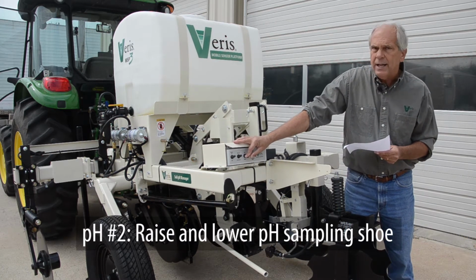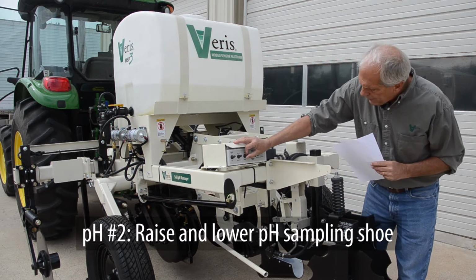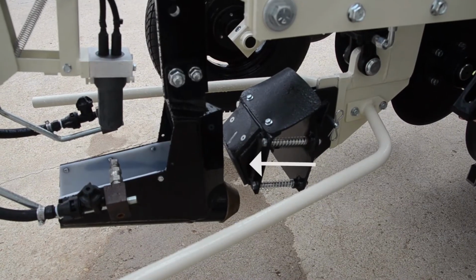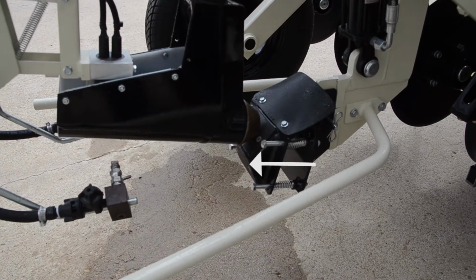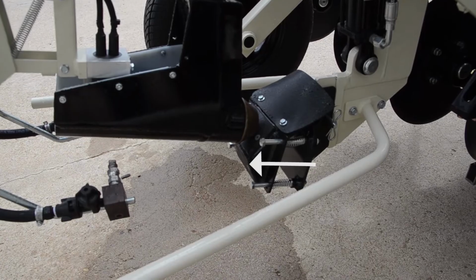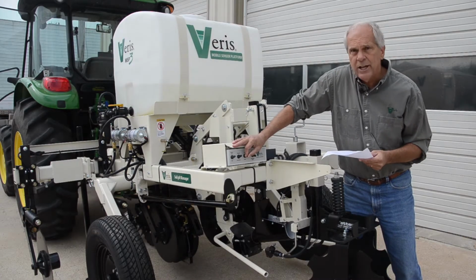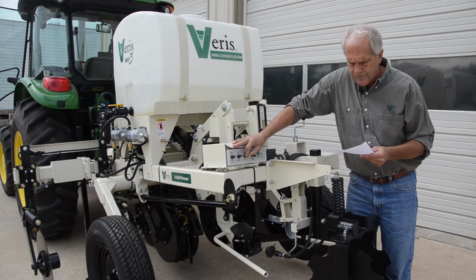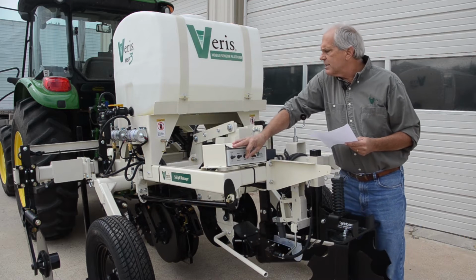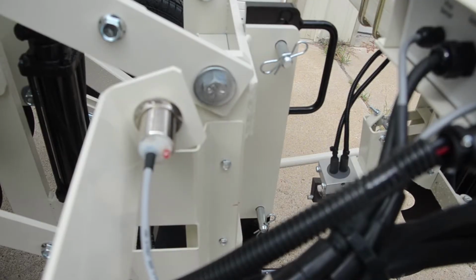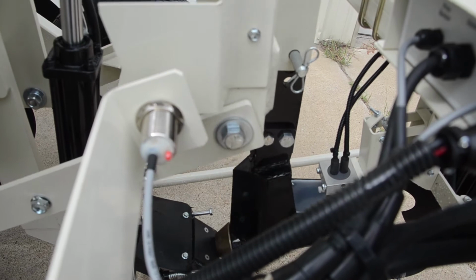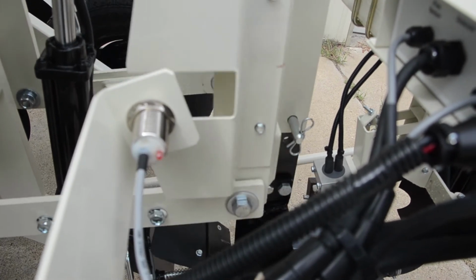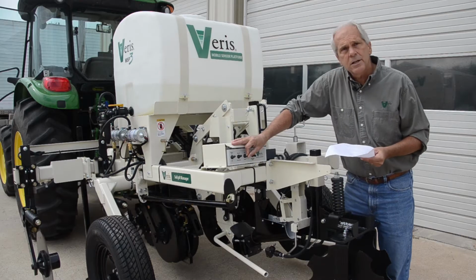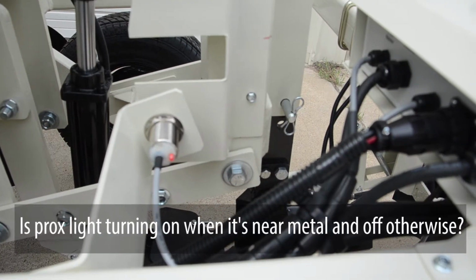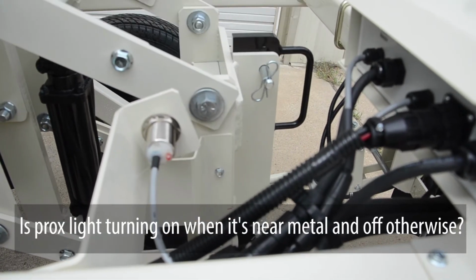As we do that, we want to make sure that the scraper is making good contact with the cutting shoe, compressing the springs and scraping the front of that cutting shoe. Also check that the prox light is turning on and off as the sampler shoe moves up and down — it should be on when it's over metal and off when it's over an air gap.